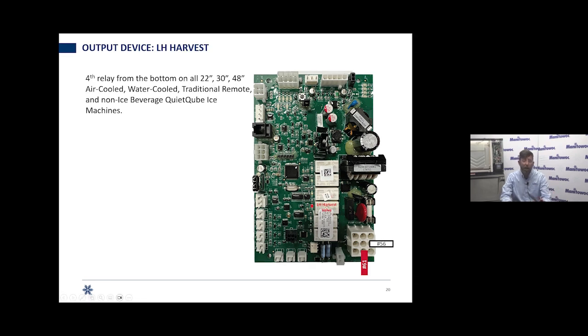All right. We talked a little bit about single circuit, single plate, and dual circuit, dual plate machines. The left-hand harvest valve relay is utilized on every machine that has one evaporator, regardless of how many circuits it has. So we energize that relay during our equalization period for a softer startup, and in harvest it will energize on a dual circuit. So think a big 48-inch wide ice machine, left circuit, right circuit, two harvest valves right together.